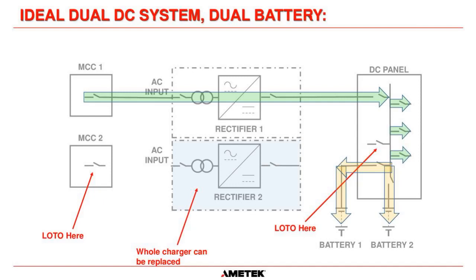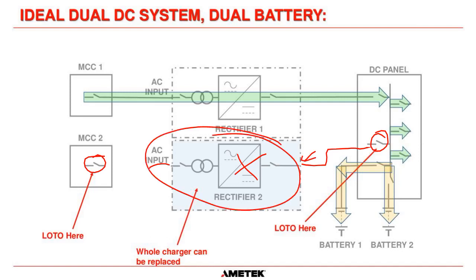Okay. And then if we have a problem with Rectifier 2 and we can't fix it, can't get parts, there's some issue and you have to replace this charger, then all you have to do, remember this cable here was connected here, is open that disconnect, put a lockout tag out on there, open this MCC circuit breaker there, and put a lockout tag out there. And then remove the cables here, remove the cables here, and that allows you to take this whole charger out and replace it with a new charger.